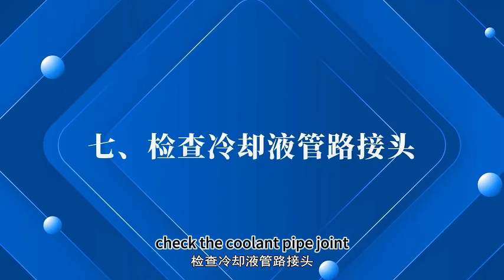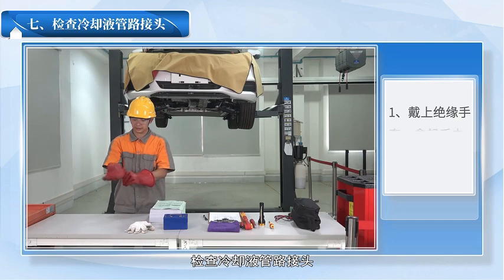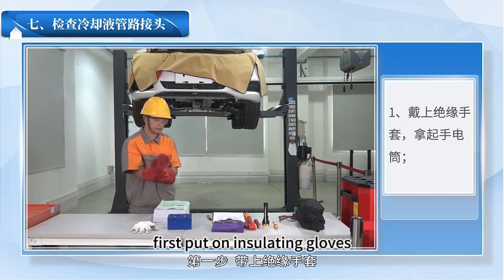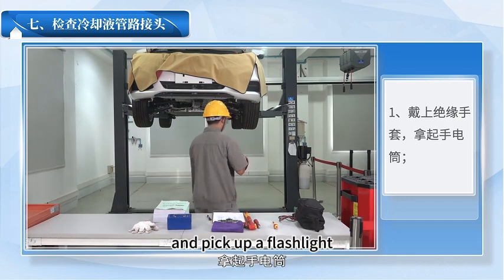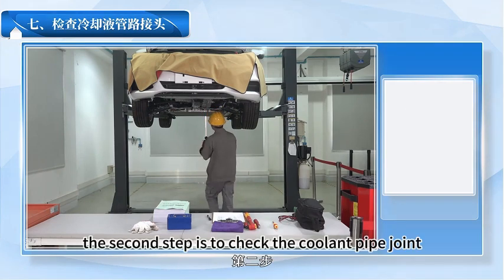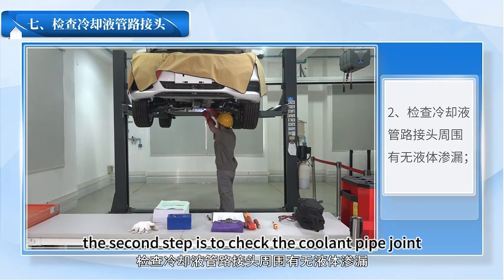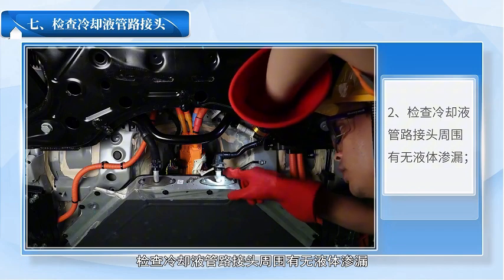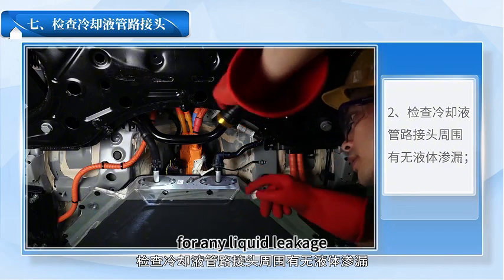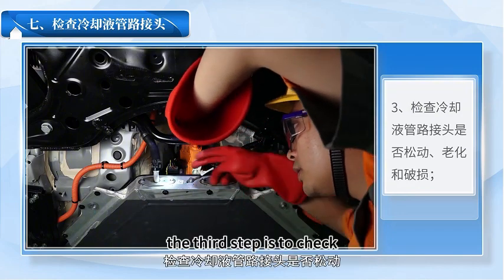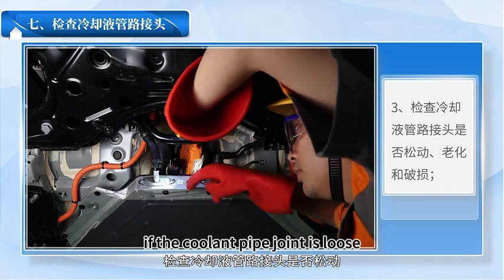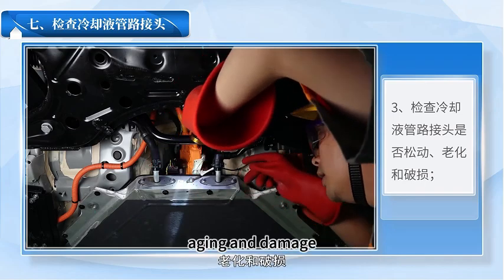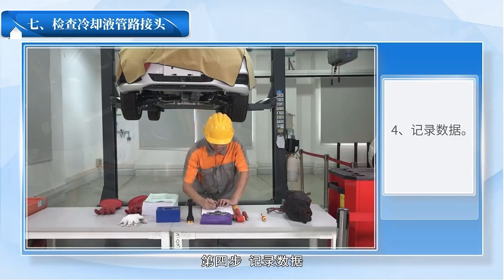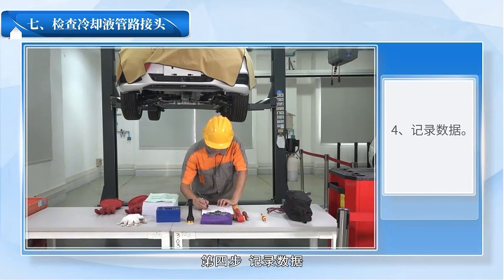Check the coolant pipe joint. First, put on insulating gloves and pick up a flashlight. The second step is to check the coolant pipe joint for any liquid leakage. The third step is to check if the coolant pipe joint is loose, aging and damaged. The fourth step is to record data.